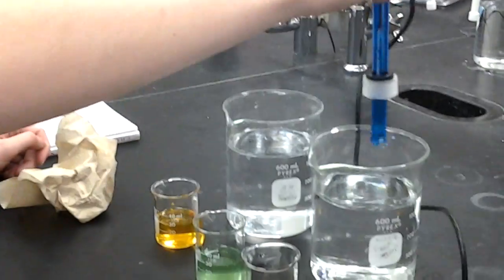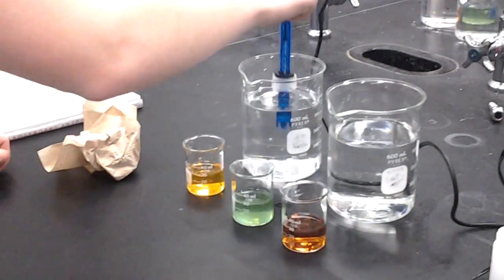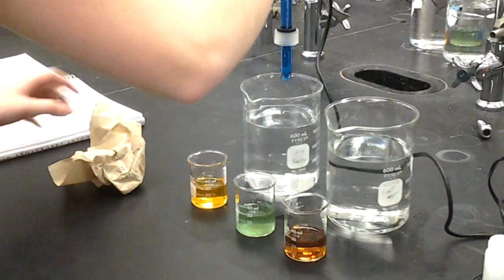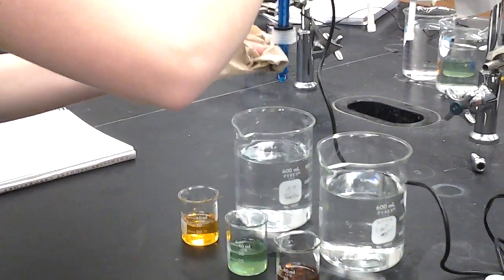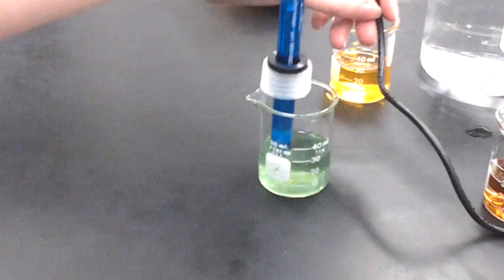Amanda used the pH meter first. After removing the probe from storage, she began calibrating it using a 2-point method. She rinsed the tip twice in deionized water and dried the sides of it, making sure not to touch the thin glass membrane at the end. While stirring with the tip of the probe submerged in the buffer solution with a neutral pH of 7, she set the first point of the meter to 7.